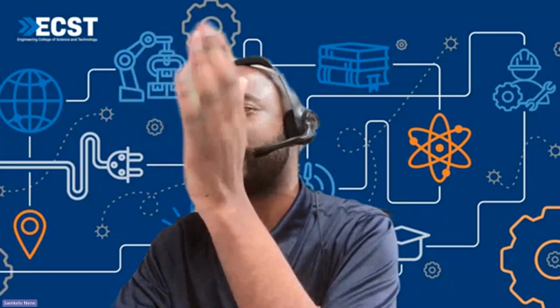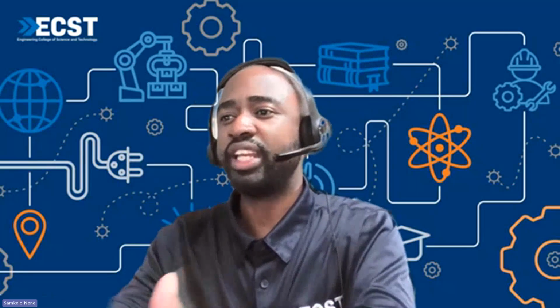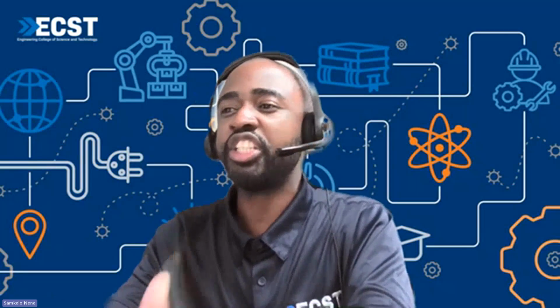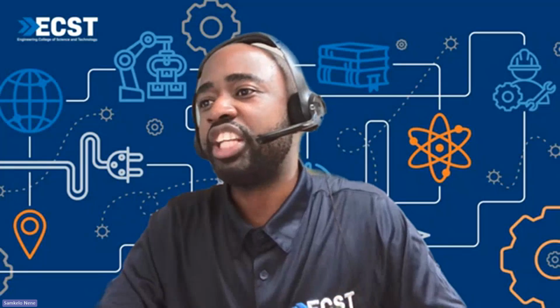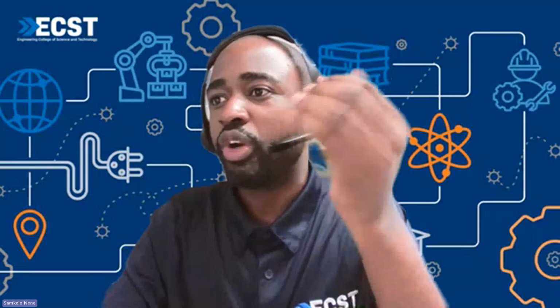As I've explained, we're decommissioning, and we are bringing in more renewables. And one of the plans that Eskom has is to deploy synchronous condensers, which will provide inertia, or natural inertia, that we need to stabilize the grid. Because without the natural inertia, chances are the inverter-based or injected or synthetic inertia, if it's poorly coordinated, will lead to grid collapses. So we can't afford that. Hence, we have some things in place such as condensers.